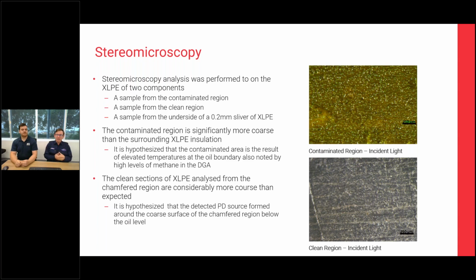The clean region, while a little bit more coarse, was significantly smoother. Several pieces of research through IEEE and CIGRE, and plenty of papers, suggest that if the XLPE is coarse, like you would see in this, then pockets of partial discharge can occur. But as Thomas alluded to earlier, it wasn't the typical void type partial discharge that we expected. This was more of a surface distributed partial discharge area, and that accounted for the higher pulses per cycle.